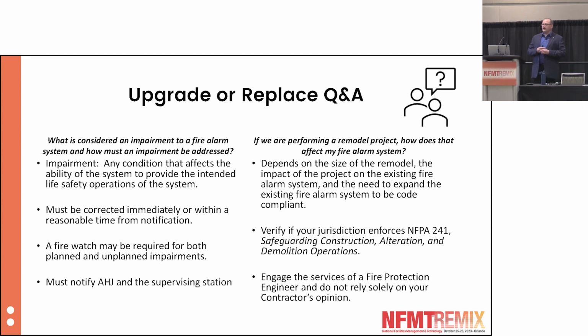But if you go to that same fire alarm system and you find that there's a short circuit on the signaling line circuit that's communicating with those 50 devices, and now the whole signaling line circuit is down, so you're not communicating with any of those 50 smoke detectors, that's an impairment. Impairments are very critical because NFPA 72 says these must be corrected immediately or within a reasonable time from notification. The term reasonable in NFPA 72 is simply defined as without unreasonable delay. So you can read into that what you will, but that's what the code says. Now if you have an impairment, some additional responsibilities come to that service provider.